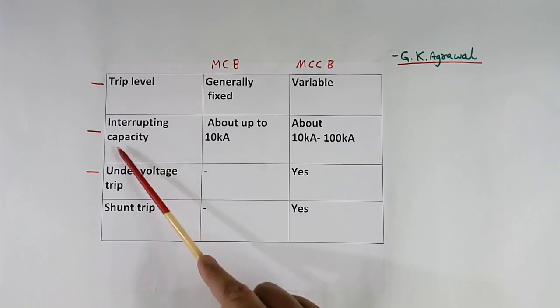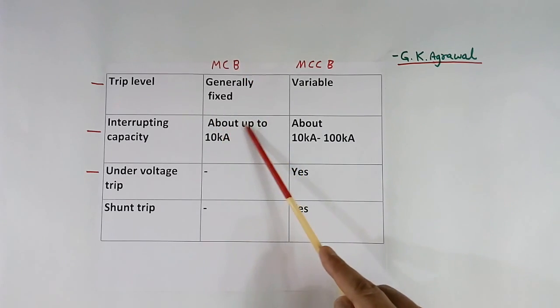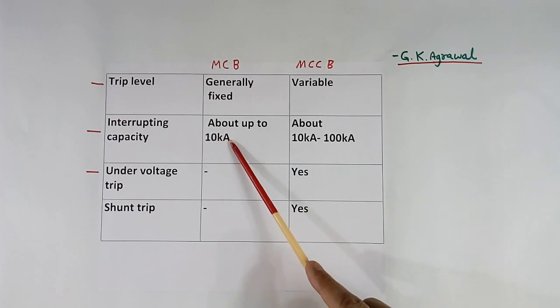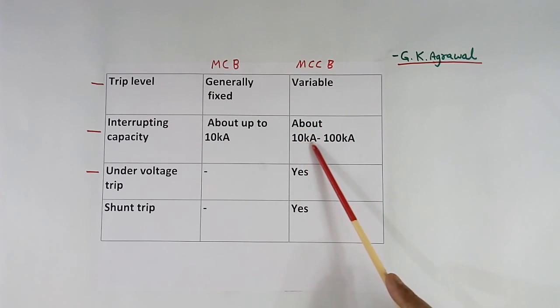Interrupting capacity, i.e., breaking current capacity. In MCB, it is about up to 10 kA. In case of MCCB, it is about 10 kA to 100 kA.